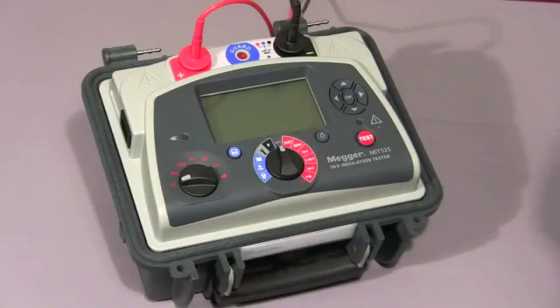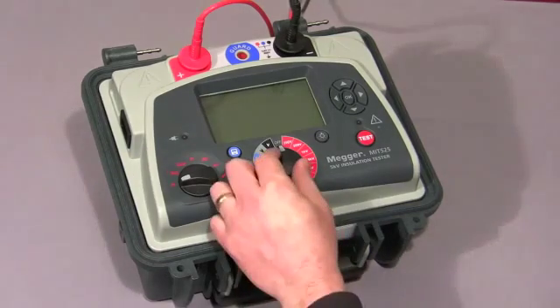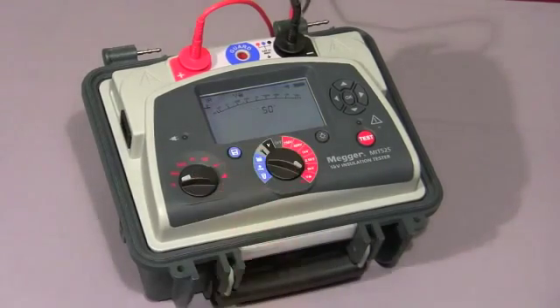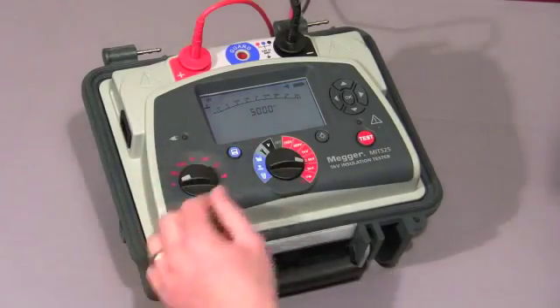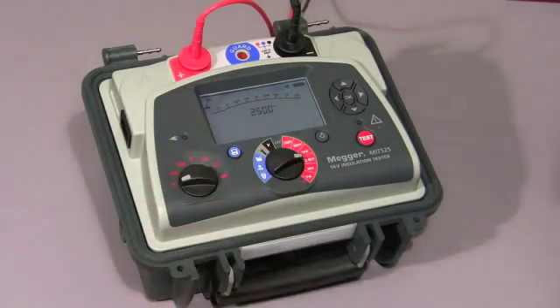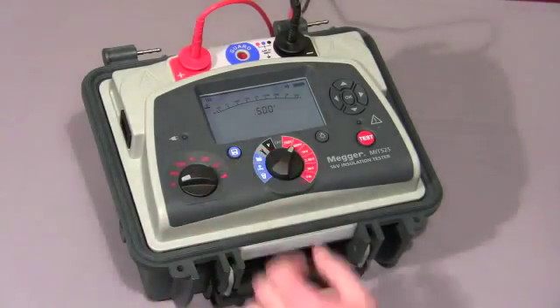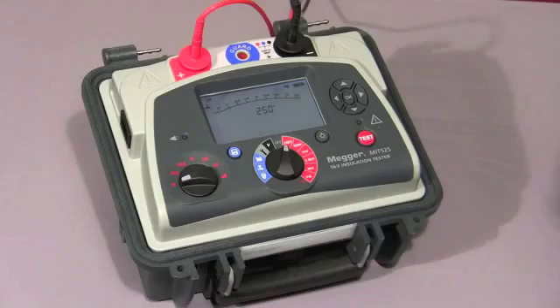Right, now having just looked at all the different diagnostic tests, I'd like to show you some of the other features the product has. Firstly, we'll have a look at the variable voltage range. In this range, the user can set the voltage from 50 volts to 5 kV if it's a 525 or 10,000 volts if it's a 1025. We have a number of preset voltages, 5 kV, 2.5 kV, 1 kV, 500 volts and 250 volts.